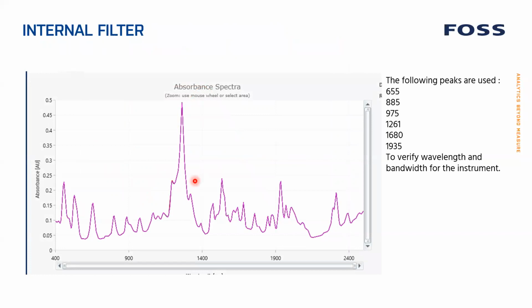This is how the absorbance spectra look for the filter inside the instrument. And you can see it has a lot of sharp peaks that we can use, and we use a number of them to verify the wavelength and the bandwidth for the instrument.